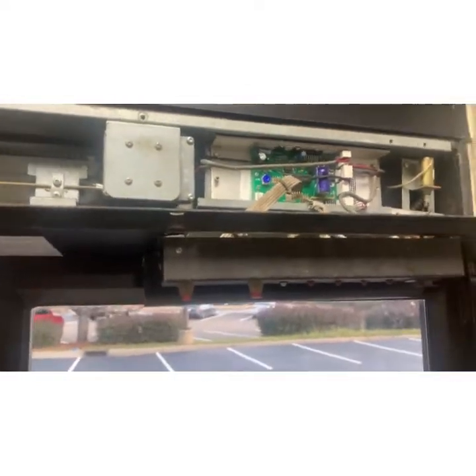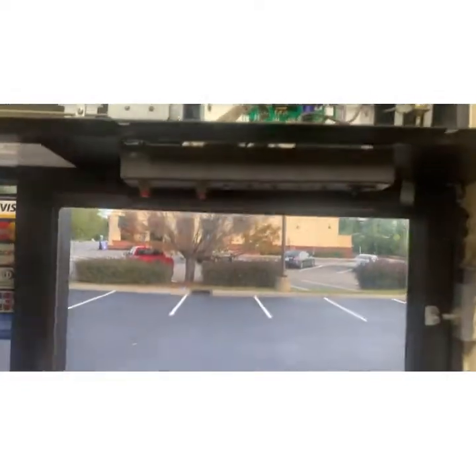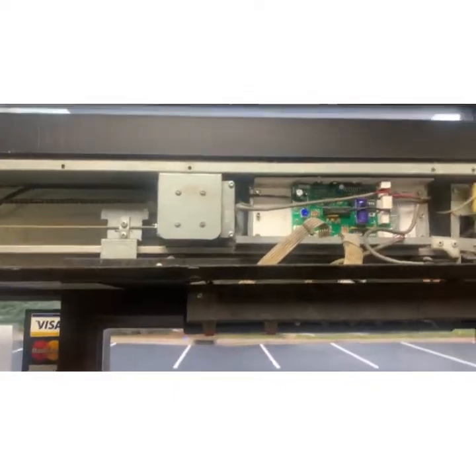I'm working on an automatic drive-thru window closer that they say just doesn't operate properly. I got here and turned it on — it will recognize you and open, but then it takes a very, very long time to close. Sometimes it would hang up while getting closed.